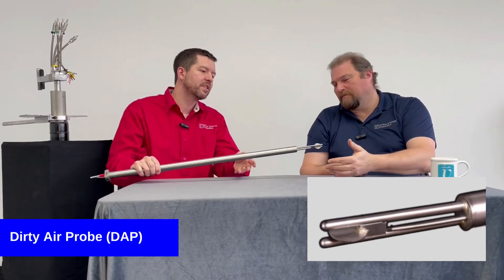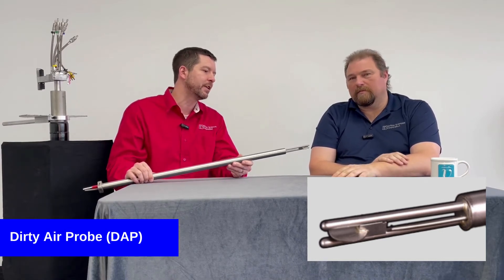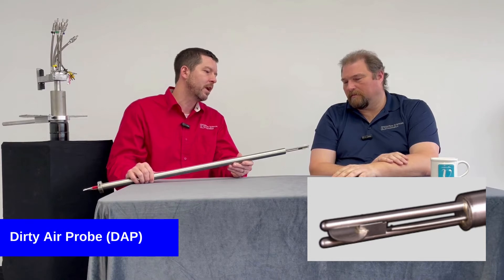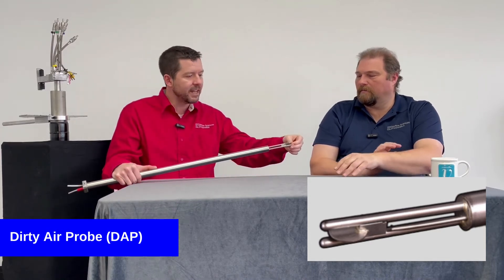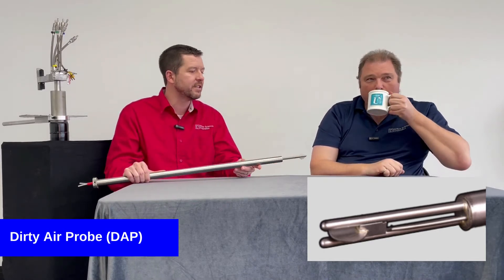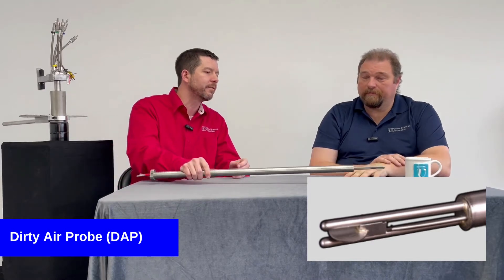Well, this probe works similar to an S-type or a standard pitot probe, where it allows you to determine the velocity by measuring pressure differential. The pressure measurement holes for this one are actually on the inside of these tubes, which makes it very resistant to plugging, and it allows you to use it in dense particulate flows.